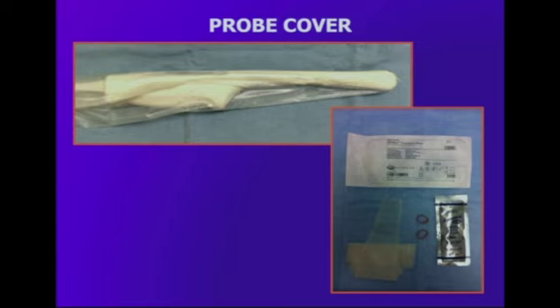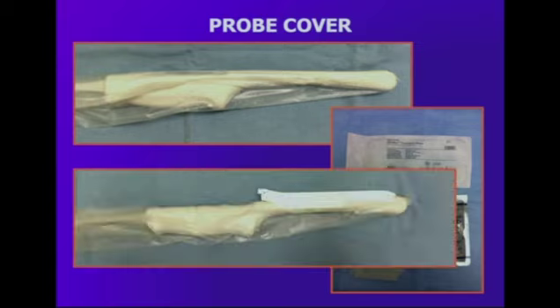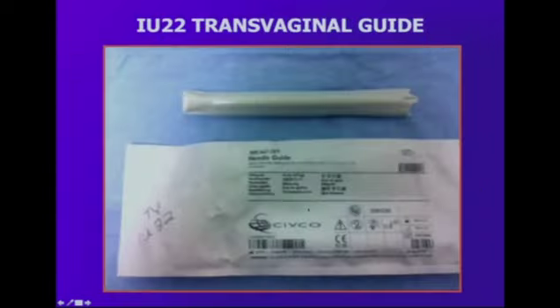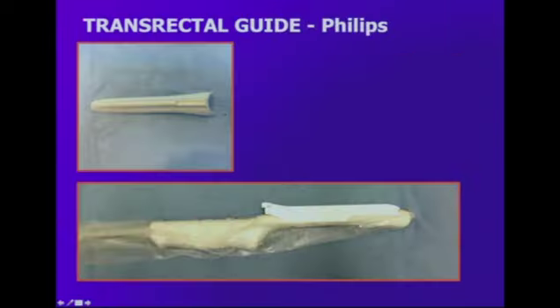Once the probe cover is in place, the next step is to affix the needle guide to the spine of the probe. And this is a sample of that here. Now, these needle guides are specific not only to the probe but also to the machine, so they all look a little bit different, and there are many of them depending on whether you're using the Toshiba, the IU-22, GE, etc. This is an example of the IU-22 transvaginal guide, and this is an example of the Philips transrectal guide that we use at our institution.